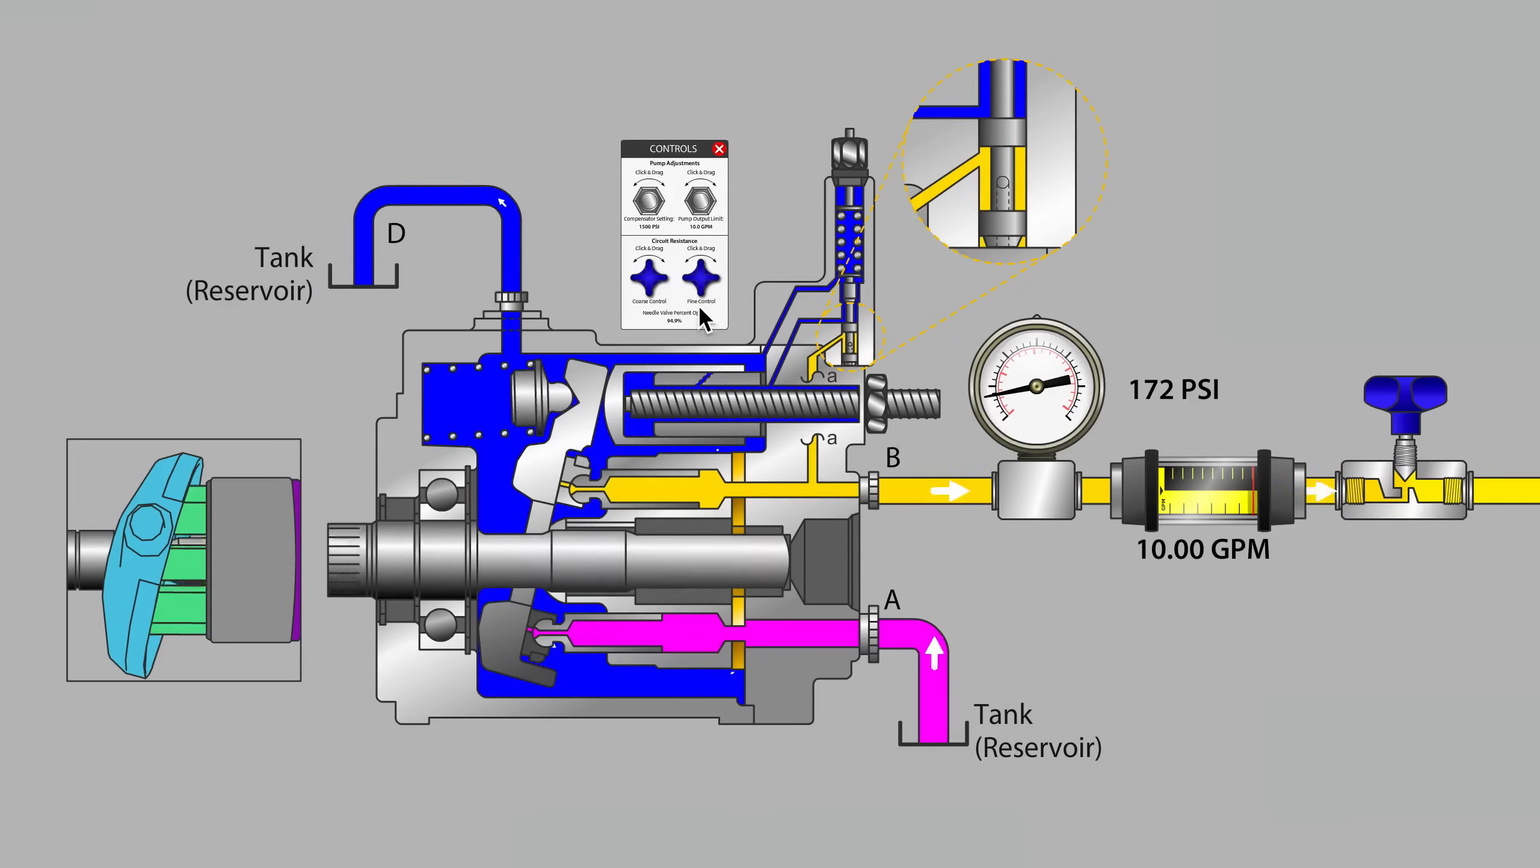So I've got the pressure compensator set to 1500 psi and remember that in this basic system we will develop system pressure just using a basic restriction on the pump's outlet, the needle valve over here on the right.